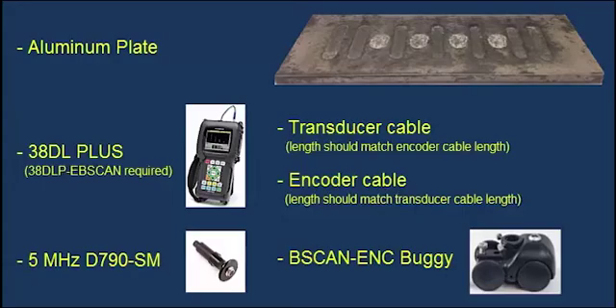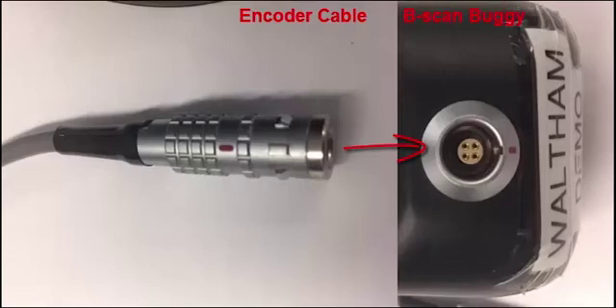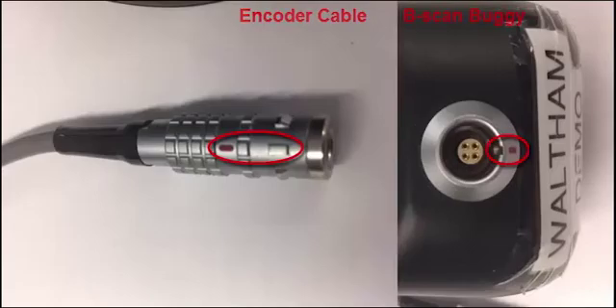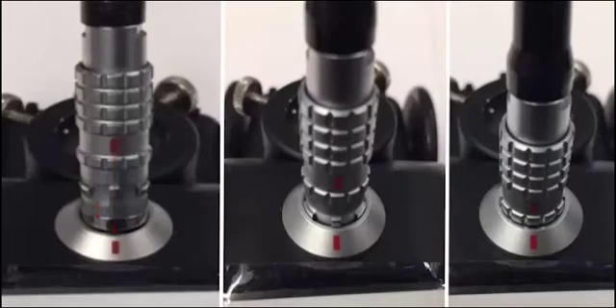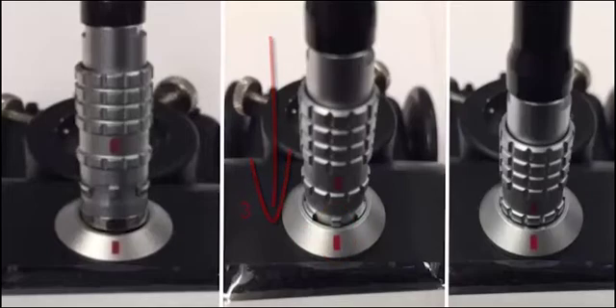First, we will connect the encoder cable to the B-scan buggy. The encoder cable and port on the buggy are keyed, so that the cable can only be inserted one way. Both the connector on the cable and the port on the buggy have red markers to assist with connecting the cable properly. Make sure to line up the red markers on the cable and on the buggy. Once they are lined up and the keyed section of the encoder cable is seated properly in the port of the B-scan buggy, we can apply pressure and the cable should snap into the connector.